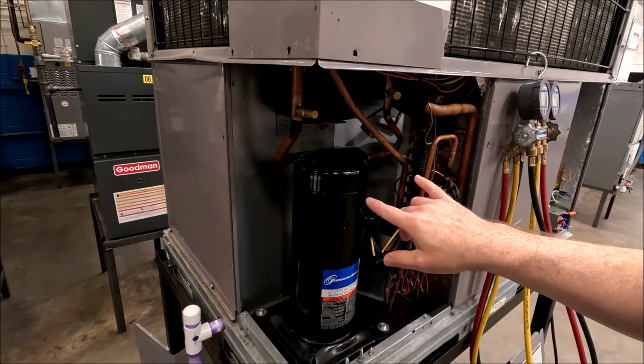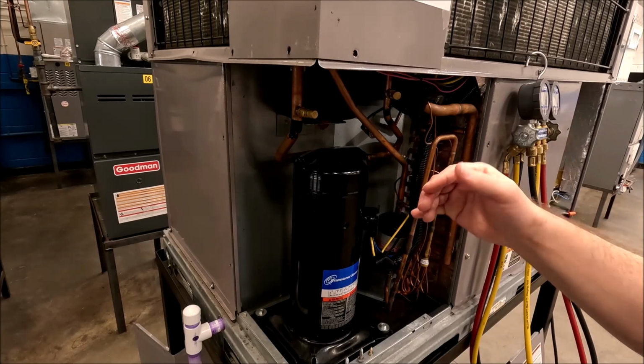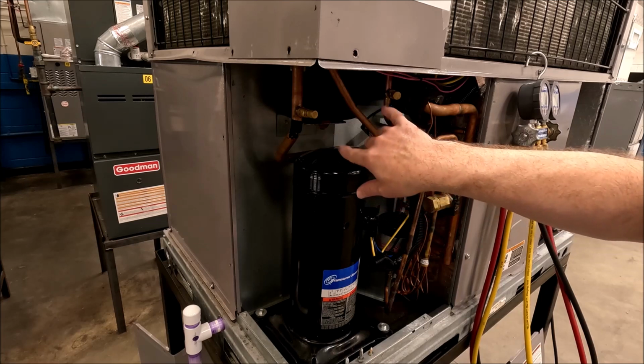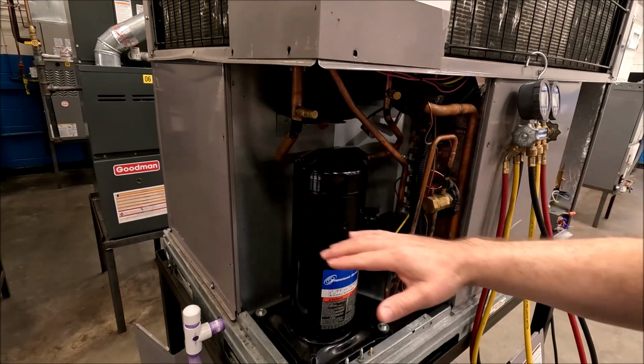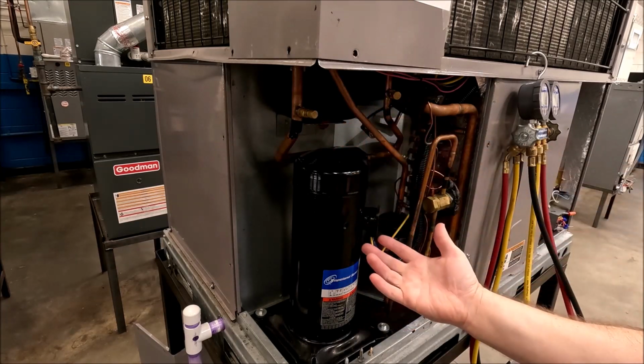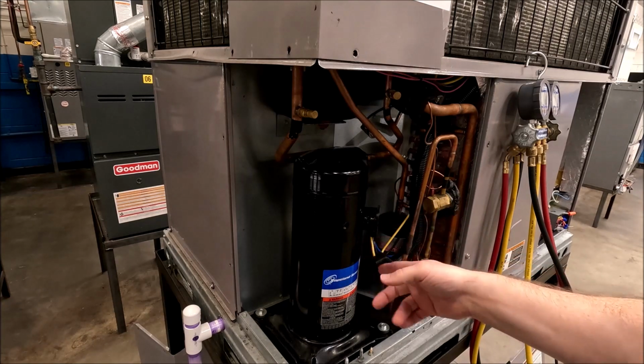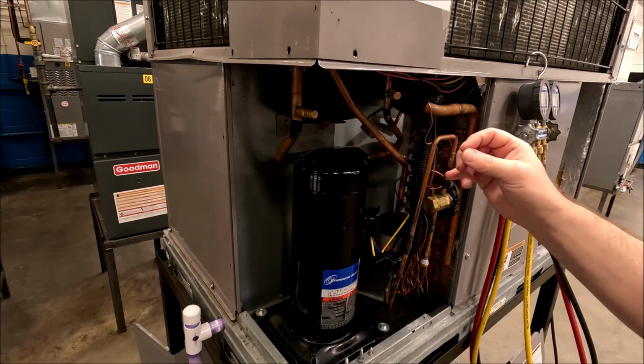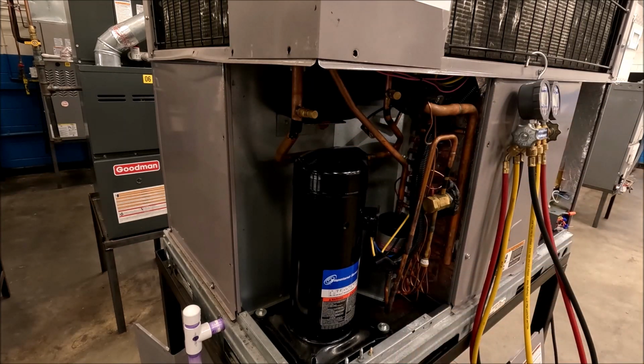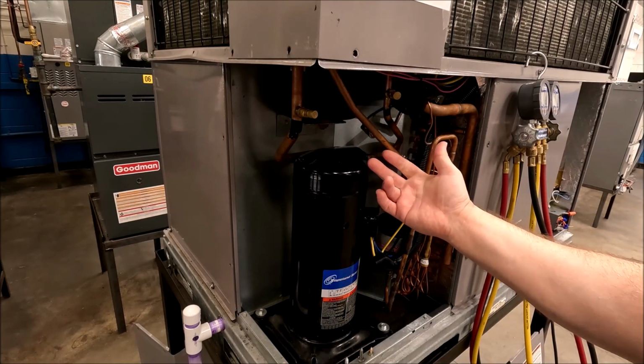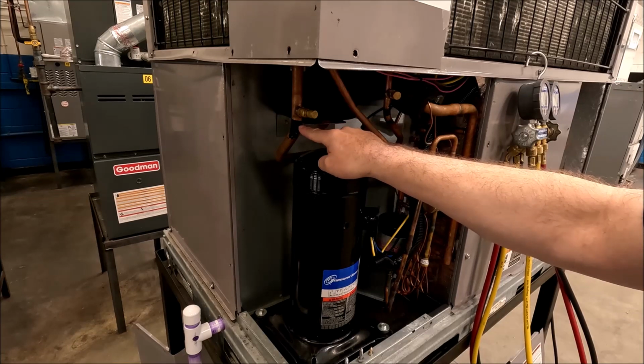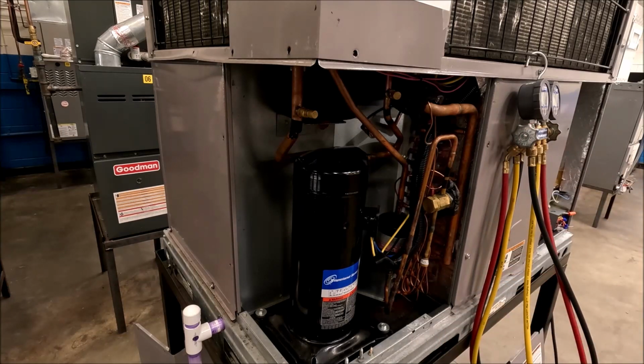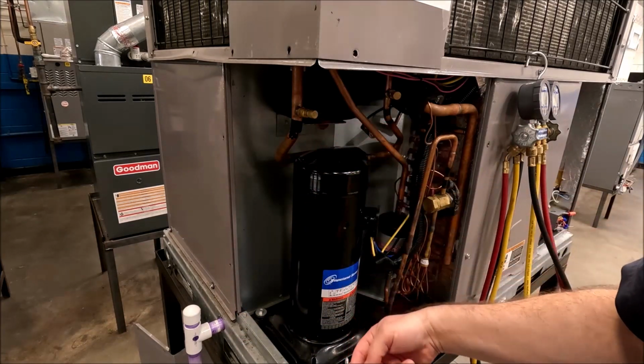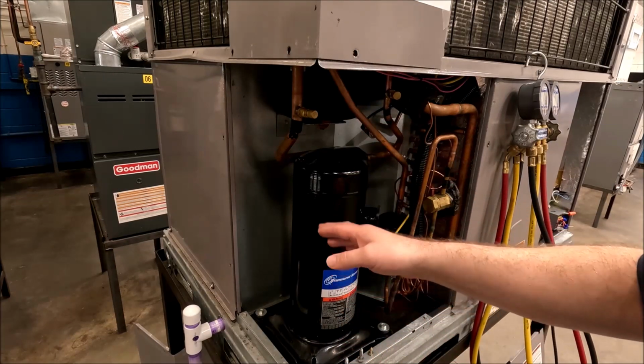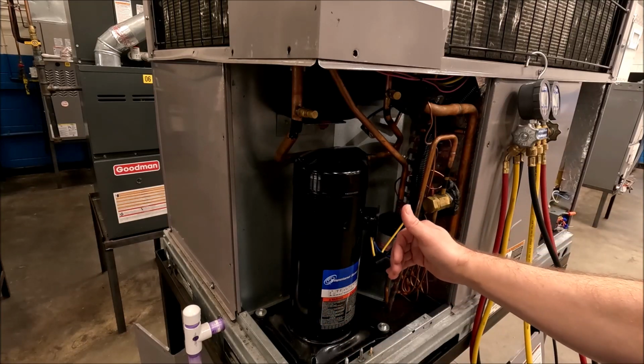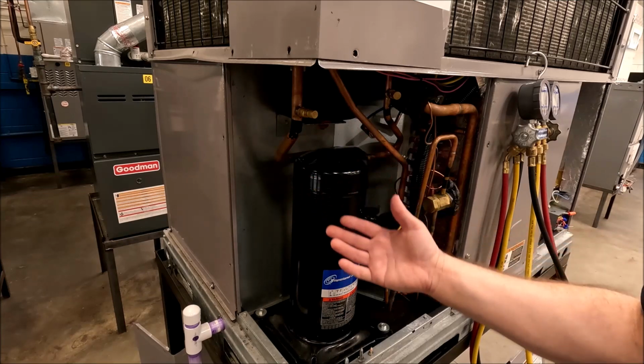So when you open up a package unit, somewhere, somehow, and there's a few different ways, but in this particular one, this is an ICP product, and when you take this corner cover off, you're going to see two access points, and I don't know of any package unit that doesn't give you just two, and they're usually close to the compressor. If not directly, then through the use of a capillary tube, they'll extend the point that they tap in close to the compressor out to a panel that's easy for you to get to. In some cases, they actually will cut a little hole in the service panel so you can run your hoses if it's not in an area like this where it doesn't matter if this corner cover's off, because there's no airflow going to get affected over the evaporator or the condenser, mainly the condenser.